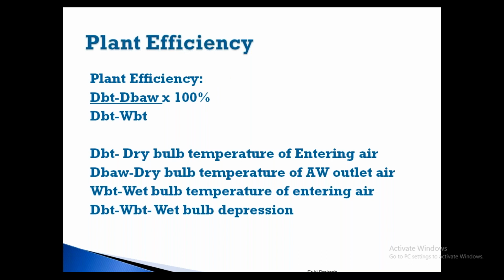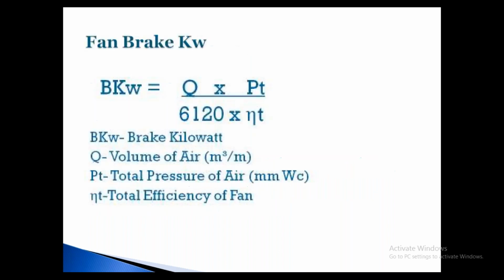So basically, if you want to find out the brake kilowatt of your fan, that is the shaft power of the fan. Q is the volume of air, multiplied by the total pressure of the air, divided by the factor 6120 times the efficiency of the fan. So here the efficiency plays a very important role. If your efficiency is less, your brake kilowatt is more. If your efficiency is more, this brake kilowatt comes down. Again, your motor efficiency also should be more. So how do you select a good efficient fan? There is a lot of scope in improving the efficiency: selection of the fan, retrofit, everything.